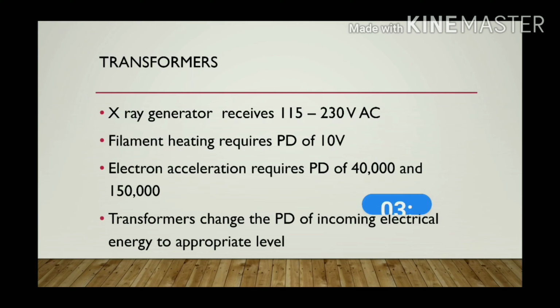So this is a transformer. This is the device that will either increase or decrease the voltage in a circuit. And these are the rectifiers that change alternating current into direct current. So the transformer, X-ray generator के पास, it receives 115 to 230 volt alternating current. बट फिलामेंट को जो है, फिलामेंट को हीटिंग के लिए कितना पोटेंशियल डिफरेंस चाहिए? 10 वोल्ट का पोटेंशियल डिफरेंस चाहिए. सो 10 वोल्ट चाहिए इसको. बट द इलेक्ट्रॉन एक्सेलरेशन के लिए फ्रॉम द फिलामेंट टू एनोड, it needs a potential difference of 40,000 to 150,000 volt. So transformer क्या करता है? It changes the potential difference of the incoming electrical energy to the appropriate level to fulfill this need of the X-ray tube.